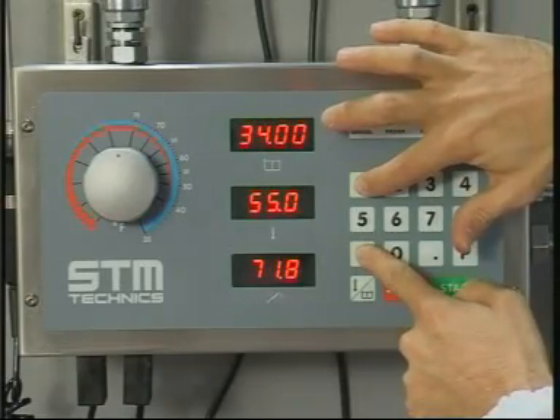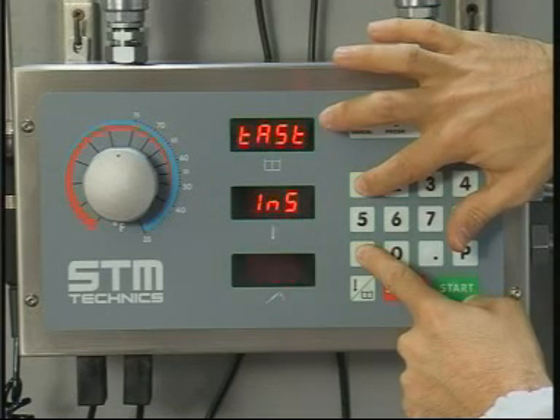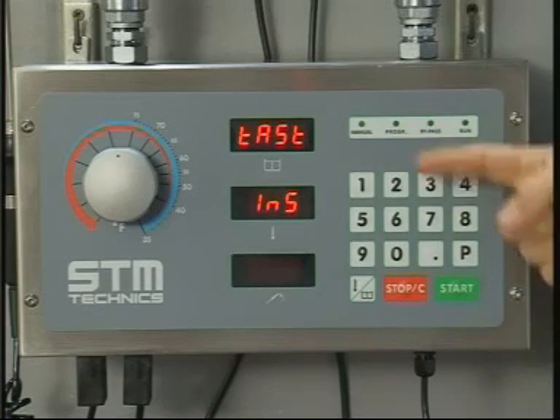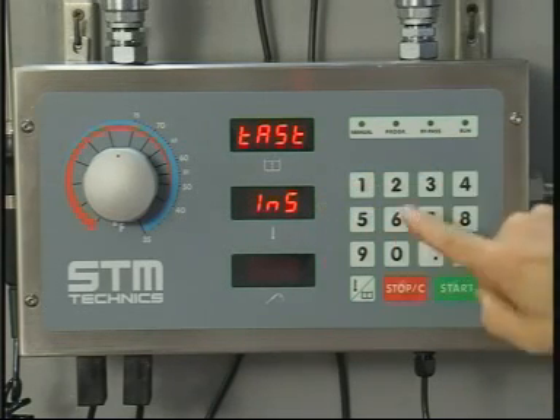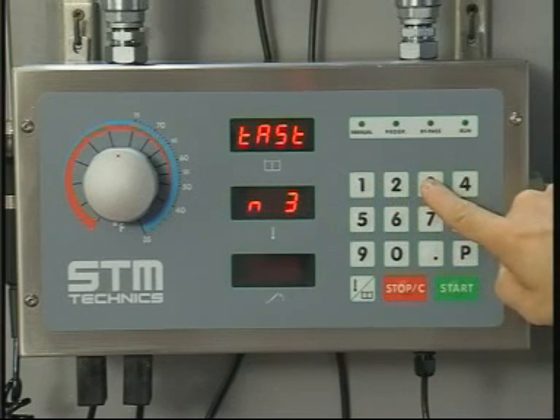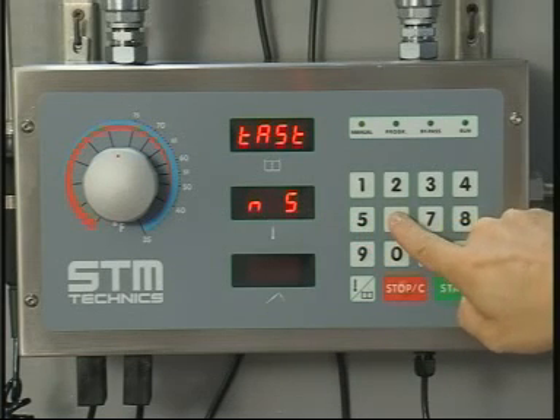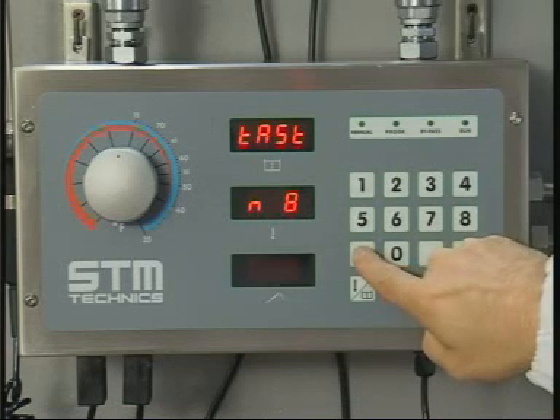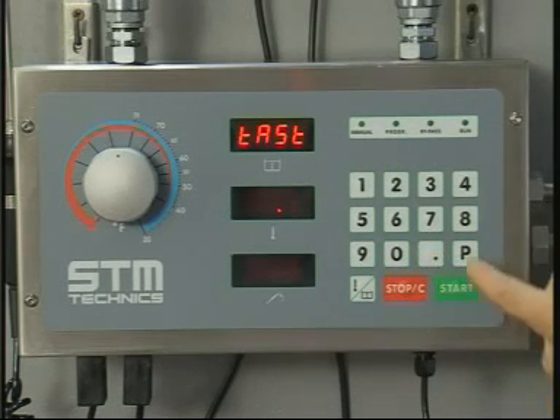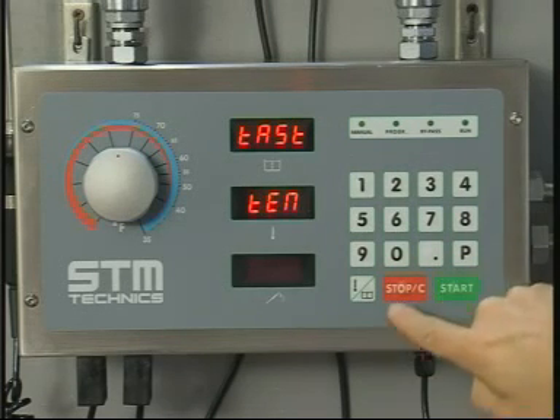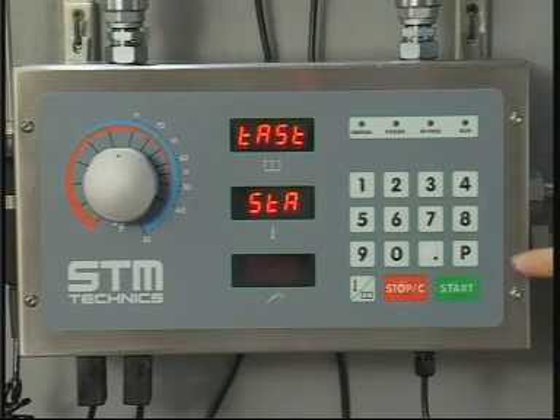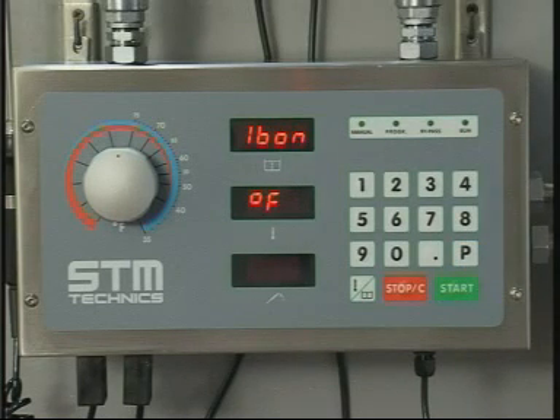Installer parameters. To enter into the installer parameters, push simultaneously the keys 1 and 9 for at least 10 seconds. Tast ins. The first display serves to check the correct function of the keyboard. By pressing the various keys, one can check that the keys are working, and on the central display will appear the relevant symbol. By pressing P twice, one passes on to the following display parameter. From this point on, to pass to the following display, it is sufficient to press the key P just once. To carry out the choice of the various options, use keys 1, 2 and 3.